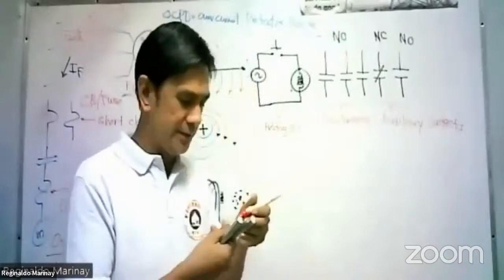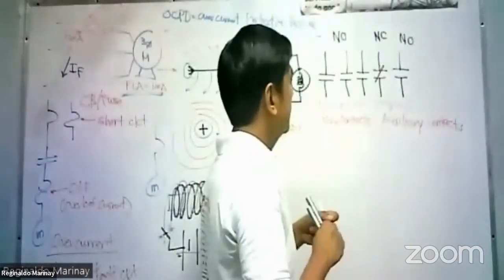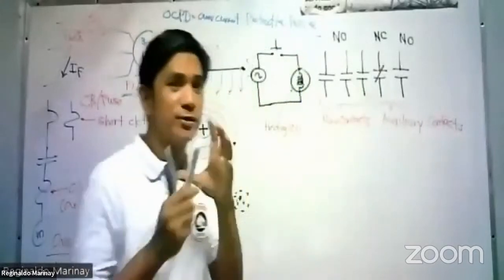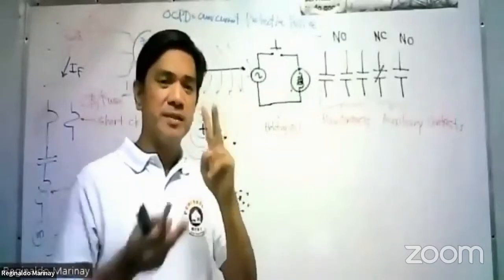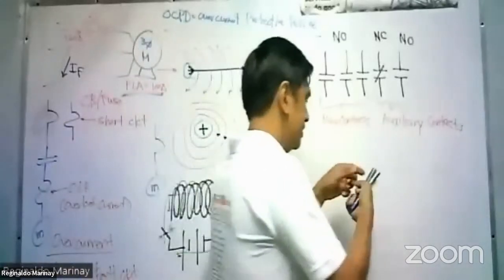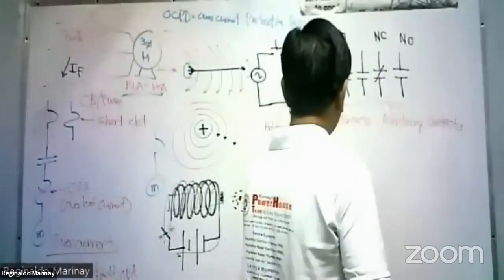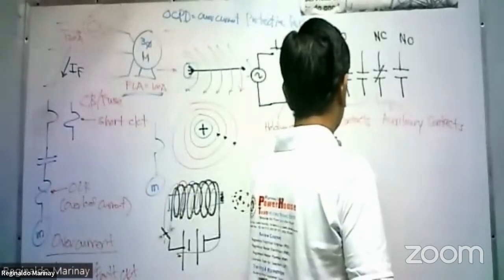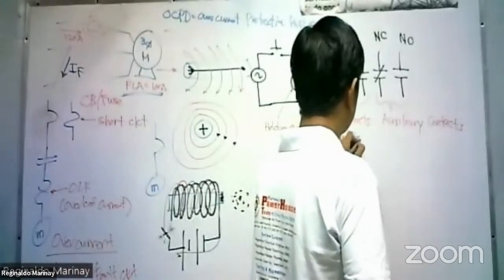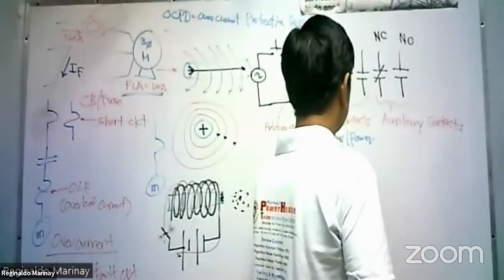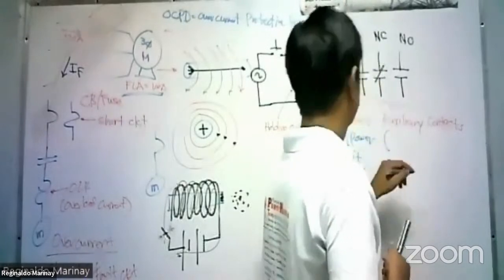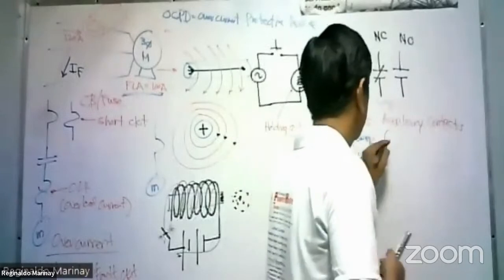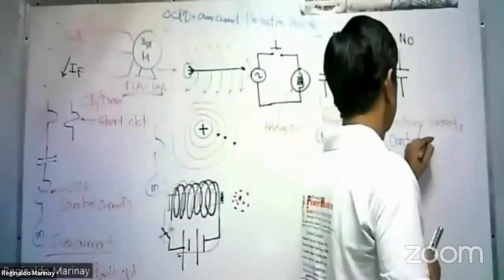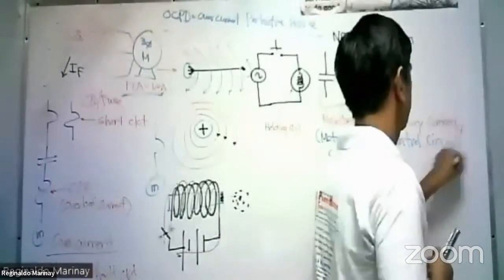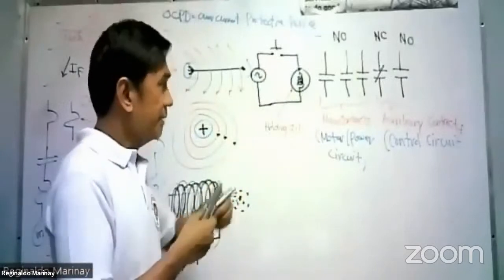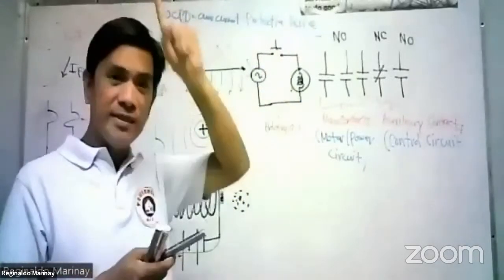What's the difference between these two contacts? The main contact is being used in the motor circuit. Always remember that a motor control diagram has two main parts, the motor circuit and the control circuit. The motor circuit is sometimes called the power circuit. And the auxiliary contact is being used in the control circuit. Keep in mind that this is only one device.